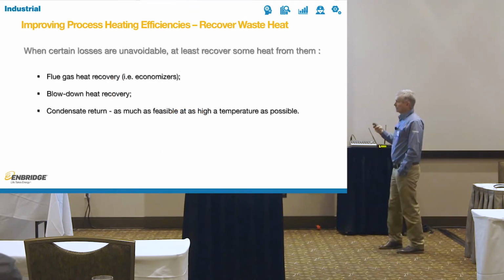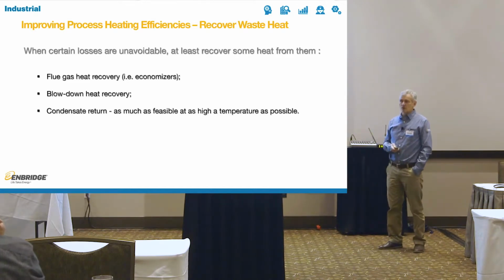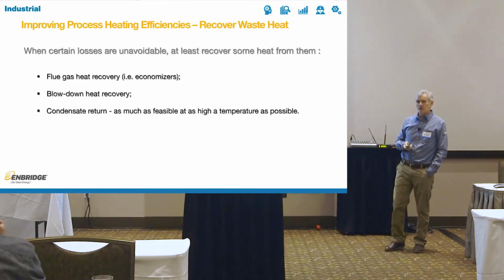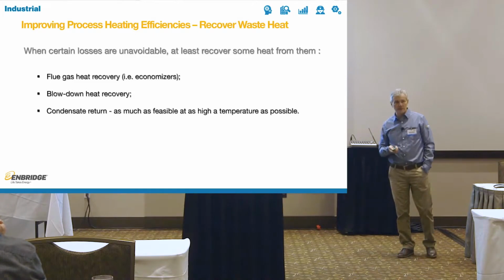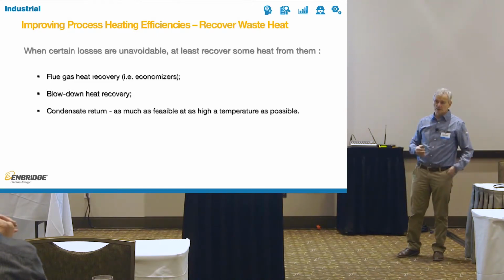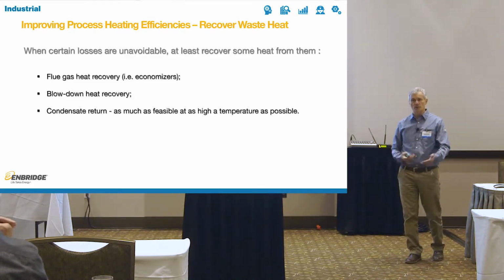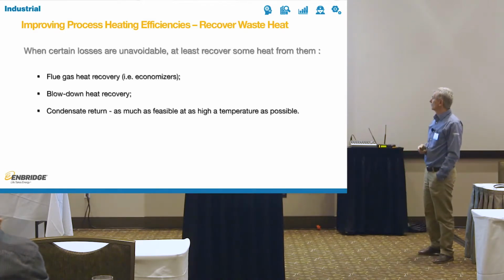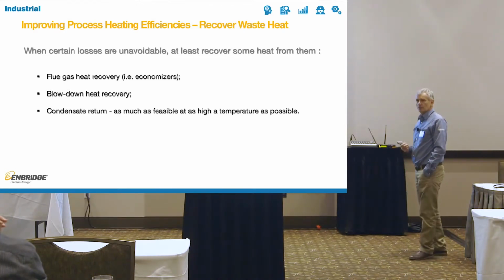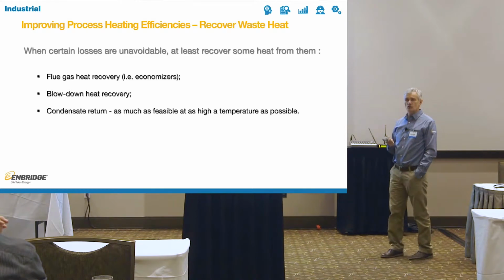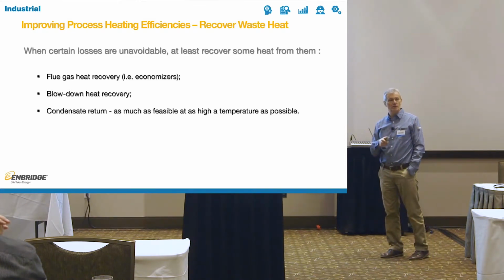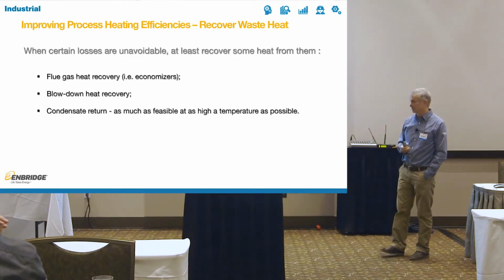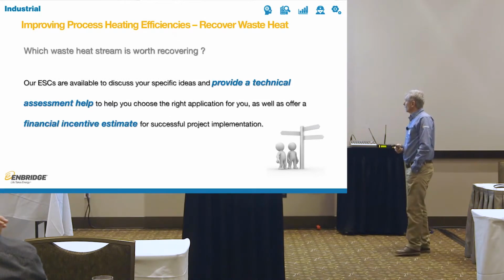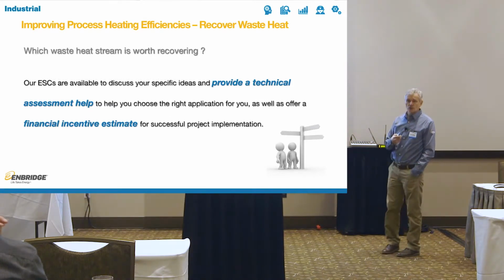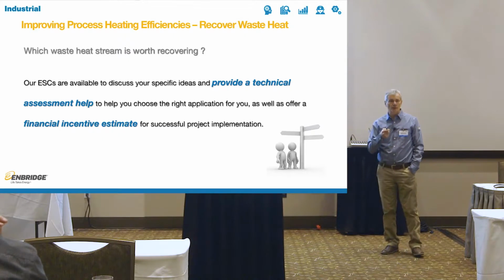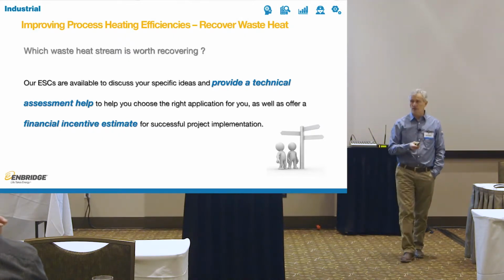So flue gas heat recovery, economizers. Everybody knows about that on the boilers. That's one way to recover your waste heat. Blowdown heat recovery is also a very popular thing. It comes on a skid. You attach your blowdown, you recover heat. Condensate return. A lot of people don't realize how much energy is still in the condensate. If you don't return it properly, you waste a lot of energy. Again, our energy solution consultants are available to discuss your particular situation, your particular setup.